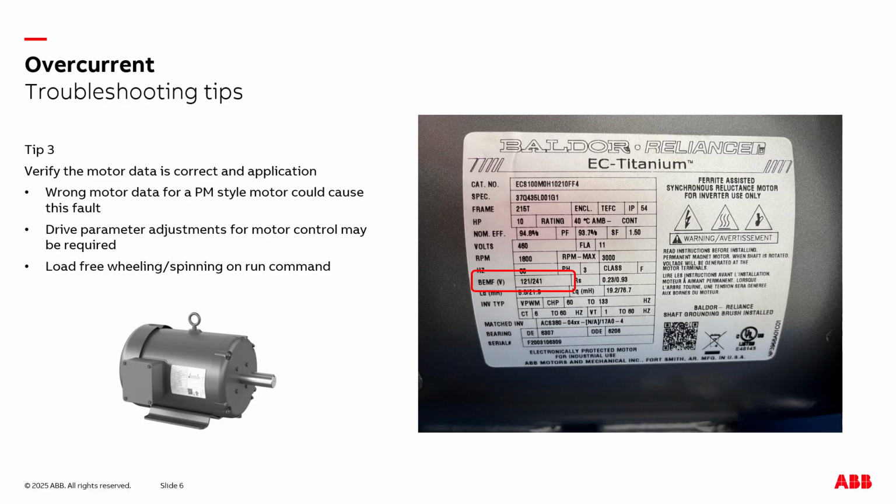In the motor parameter group in an ABB drive, we want to review specifically the voltage value programmed into parameter 9907. This value should not be your nominal voltage, such as 230 or 460, but actually the back EMF voltage. This back EMF voltage many times can be programmed on the standard motor nameplate, or sometimes it's also located on a separate motor nameplate, potentially mounted even on the opposite side of the motor from the standard motor nameplate.